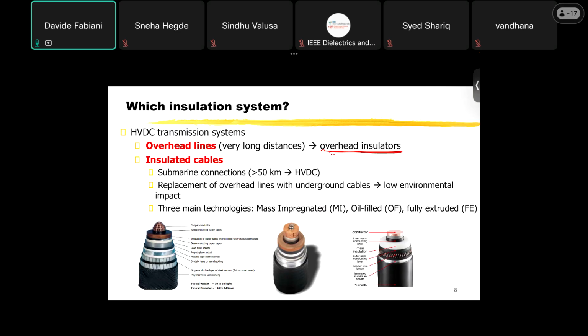So the possibility is to use insulated cables. These are, of course, compulsory if you are creating a submarine connection, because for lengths longer than 50 kilometers, HVDC is the only technology available. You cannot use AC due to the reactive power that is necessary to feed the cable.